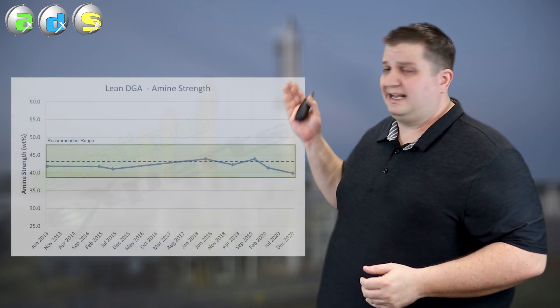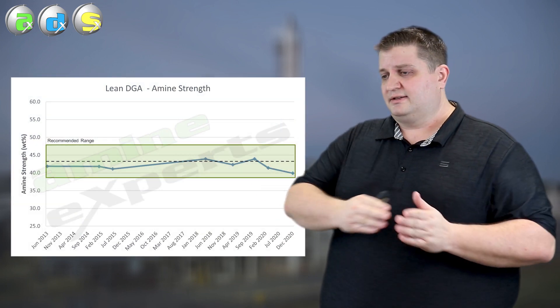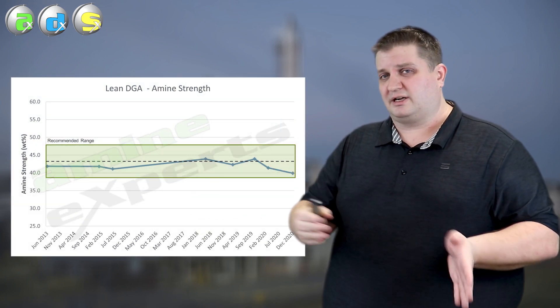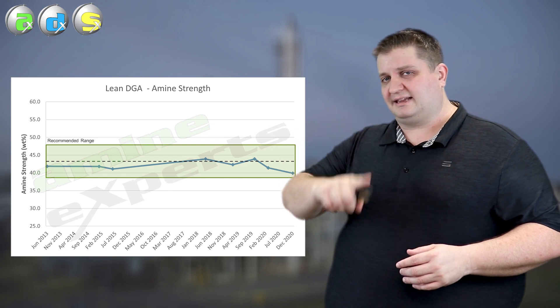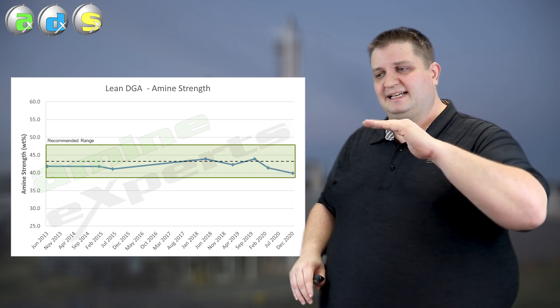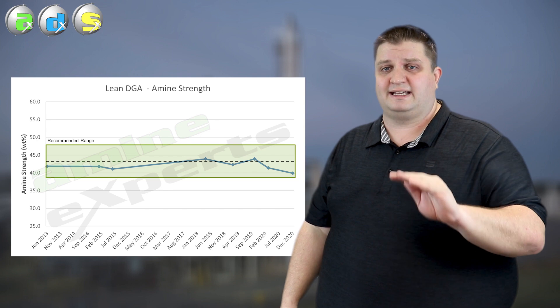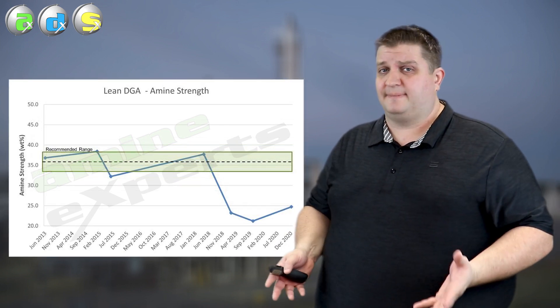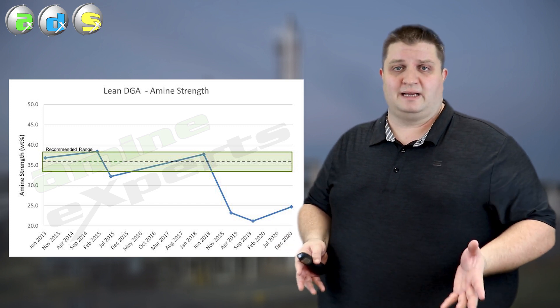As a part of that full analysis then you can go through and you can trend. So like we see here with this amine strength, over the period of a couple months or a couple years even you can see exactly how the amine trend is flowing up and down and staying nicely within that range where you want to keep it. If you start seeing sharp changes well you know that you're having a lot of upsets in your plant that you need to remedy right away.